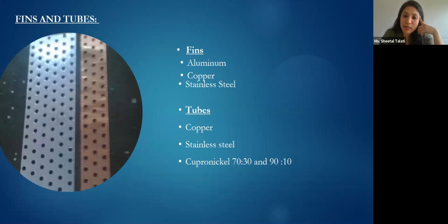Now, talking about the fin material that can be used in constructing a coil. The most common and economical one is aluminium, which is usually seen in split air conditioners, window air conditioners, and even packaged ductable units. The chilled water coils and DX type coils use aluminium fins in majority. Copper fins are 4 times higher in price than aluminium, so they are used in marine related jobs. Stainless steel fins are used where there are food processing units, and where there is a high level of corrosion.